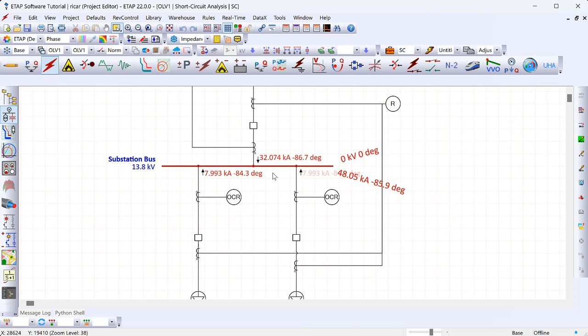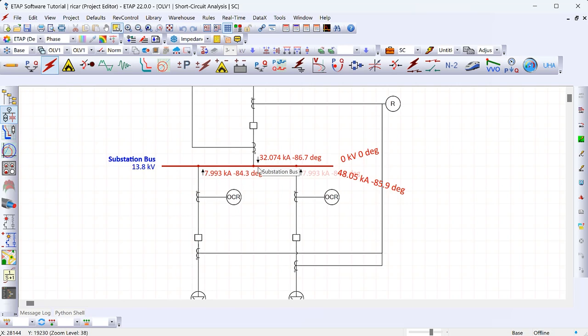One reason to run a short circuit study is equipment rating verification. For example, if this 13.8 kV bus is a switchgear, that switchgear will have a rating for the amount of fault current it can withstand. You want to make sure that during the worst-case fault you don't exceed the switchgear rating. As a real example, I had a project with two switchgear tied by a tie-breaker — paralleling two transformers made the fault current too high. We had to implement an interlocking system so the transformers could not be paralleled, preventing the fault current from exceeding the switchgear rating.